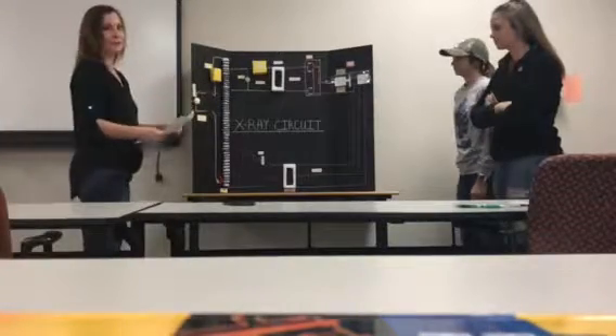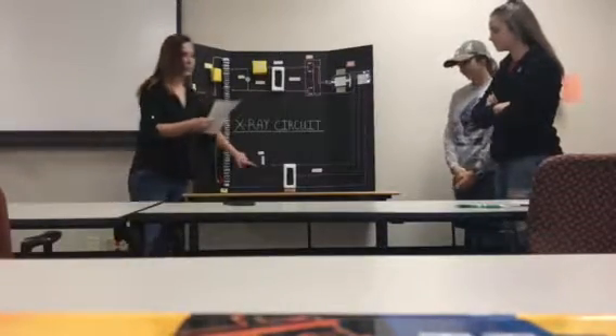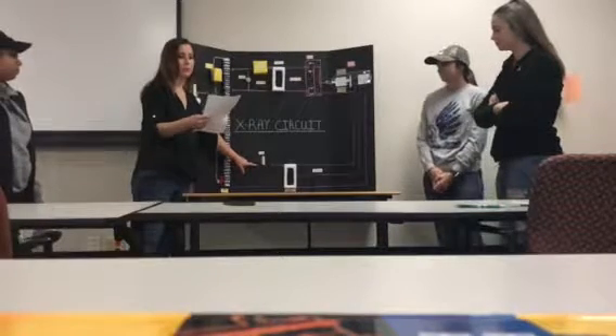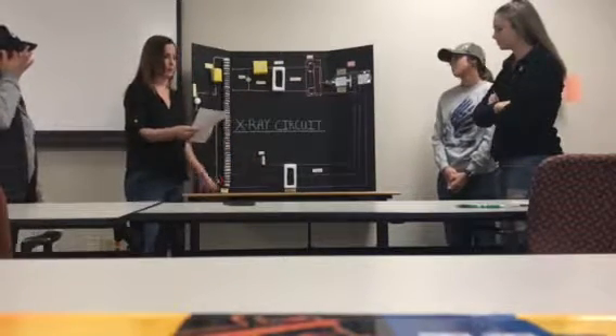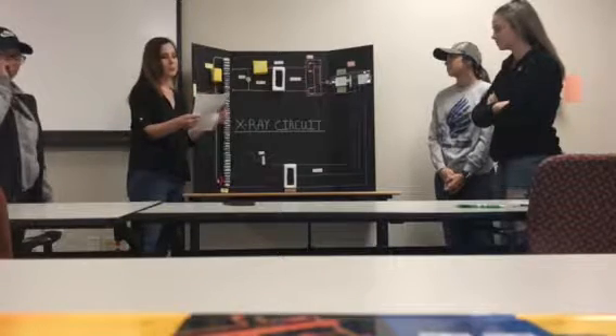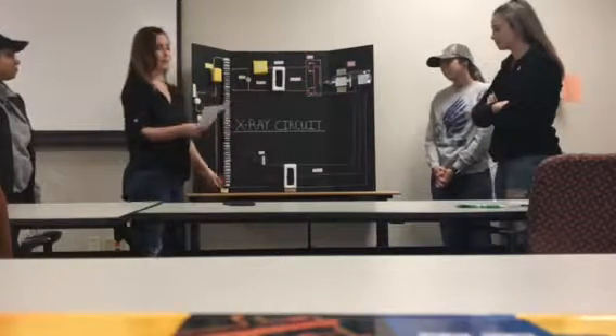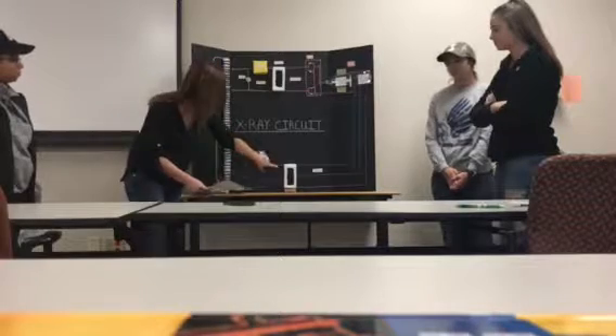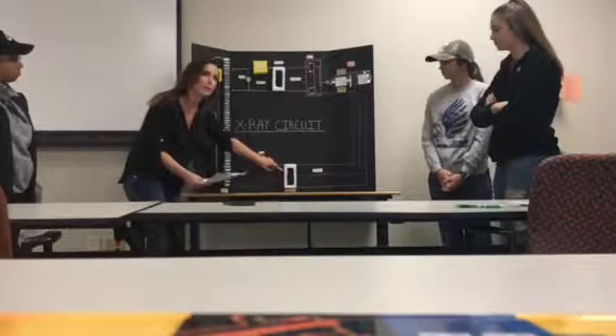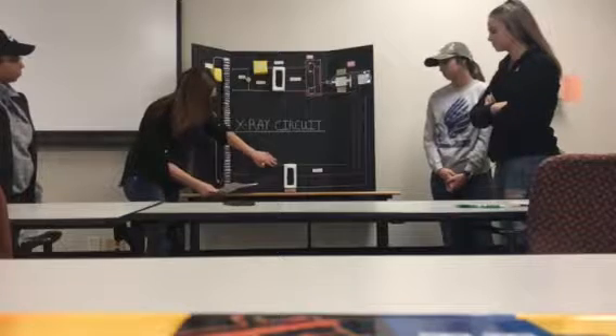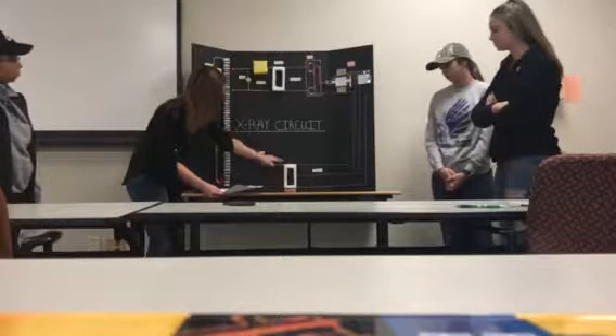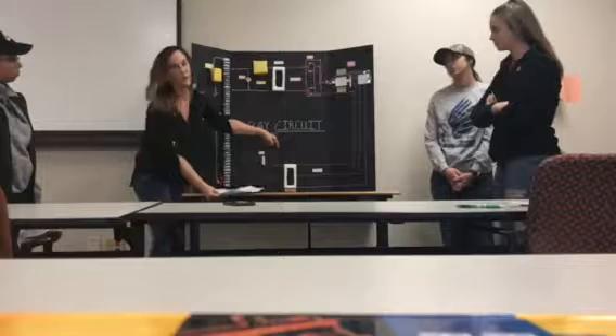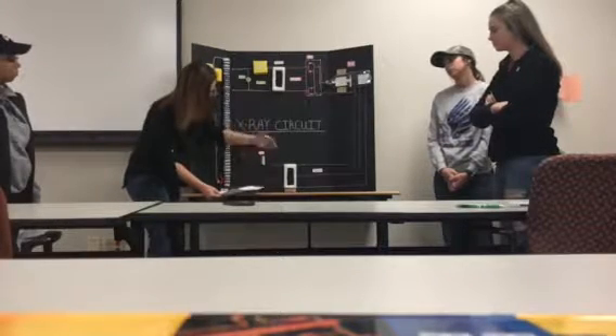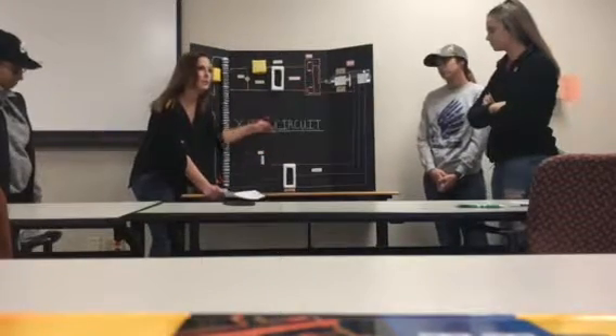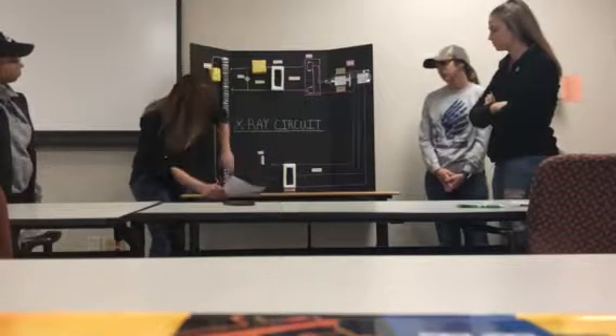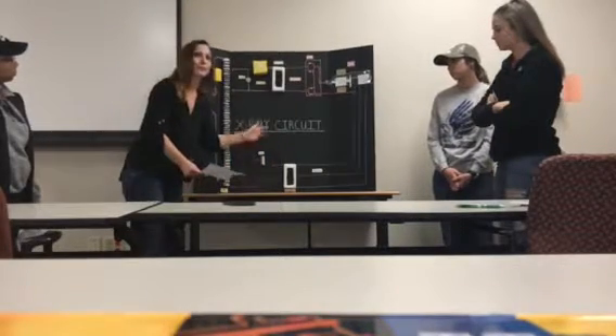Danielle? So starting with the filament circuit is the rheostat, which is a variable resistor that is controlled by the MA selector on the operating console. It's responsible for the amount of resistance and current in the filament circuit itself. Then we have the step-down transformer, which you heard earlier is a mutual induction, which means it is basically increasing the current by reducing the voltage that is applied to the filament. As voltage decreases, current increases. That's why it's mutually working together. And that concludes the filament circuit.